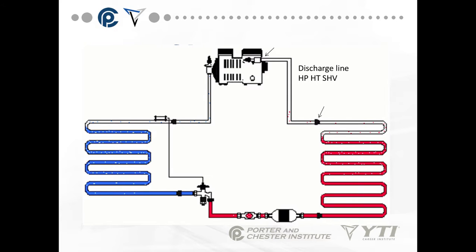The discharge line is found in the top right-hand corner of this slide. The discharge line contains a high-pressure, high-temperature, superheated vapor. We call it superheated because it has very high sensible heat — it includes the heat taken out of the space we're trying to cool through the boiling process in the evaporator, plus the heat of compression. Anytime you compress a vapor, it creates heat. That superheated vapor is pushed out through the discharge line at high pressure and high temperature into the condenser.